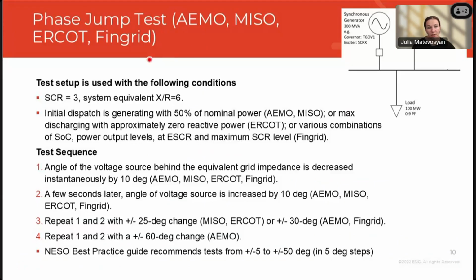AEMO, MISO, ERCOT and FinGrid define a relatively similar phase jump test. So this is tested for a short circuit ratio of 3 and a system equivalent X to R ratio of 6. There are different dispatch conditions that this is tested for. I won't read through the slides, but you can see it here. And then how the test is conducted: the angle of the voltage source behind the equivalent impedance is decreased instantaneously by 10 degrees. A few seconds later, it's increased back by 10 degrees. And then the steps are repeated for plus minus 25 degrees. MISO and ERCOT, AEMO and FinGrid do plus minus 30 degrees. And AEMO also does a test for plus minus 60 degrees.